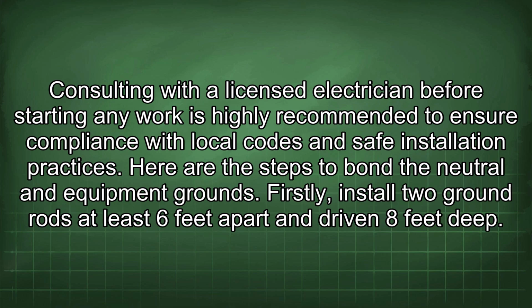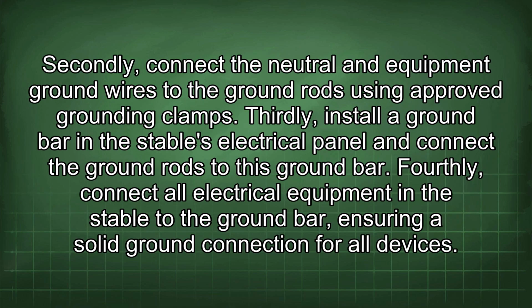Here are the steps to bond the neutral and equipment grounds. Firstly, install 2 ground rods at least 6 feet apart and driven 8 feet deep. Secondly, connect the neutral and equipment ground wires to the ground rods using approved grounding clamps. Thirdly, install a ground bar in the stable's electrical panel and connect the ground rods to this ground bar. Fourthly, connect all electrical equipment in the stable to the ground bar, ensuring a solid ground connection for all devices.